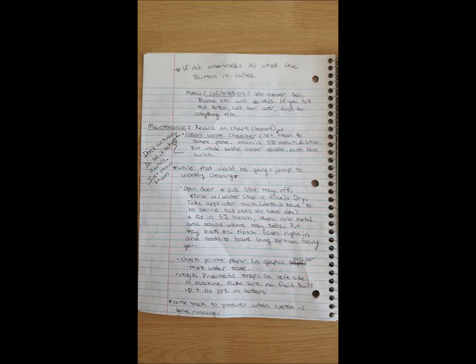Set cell clean to the sample probe. Cell clean is simply a 5% dilution of bleach, which we have to make up once a month. I need to do that fresh soon. So all you're going to do is stick that under there and push the button. It'll beep at you when it's ready. Take it out, put the lid back on. That was tough, right? Now, while this is doing its thing, you never want to be standing up watching it. We're going to go down to the weekly maintenance, and we're going to clean the SRV tray.